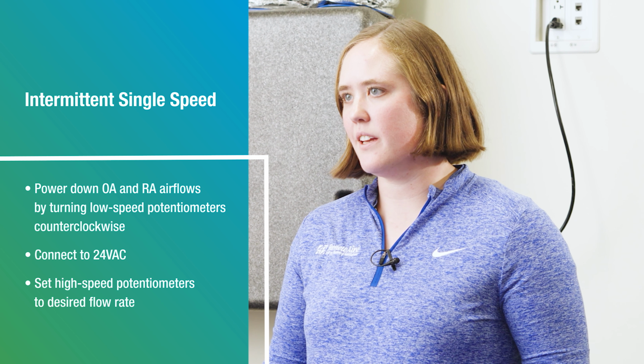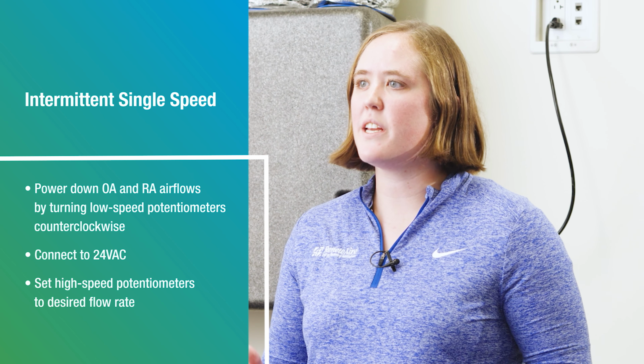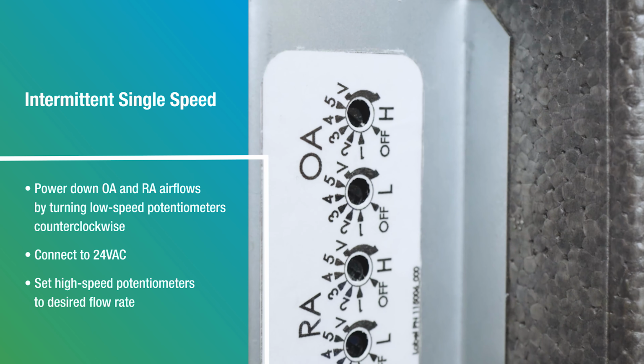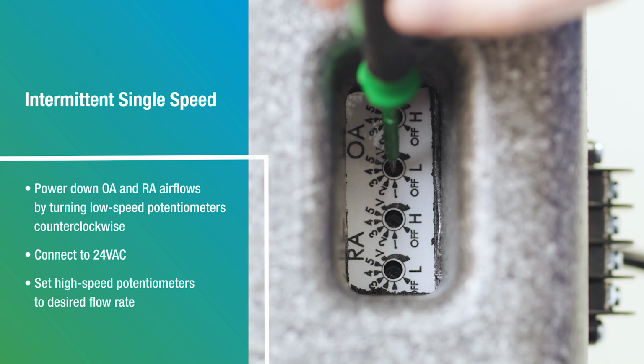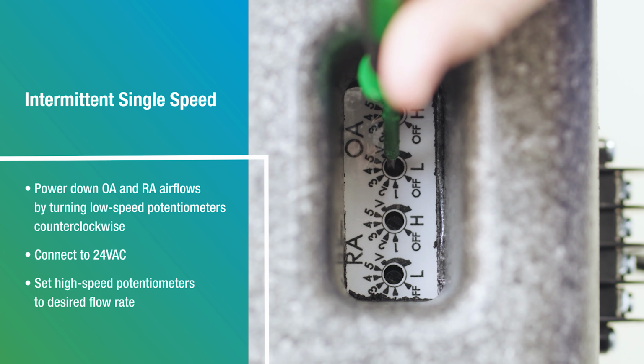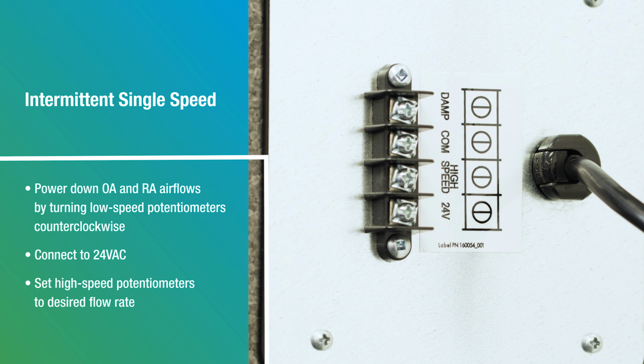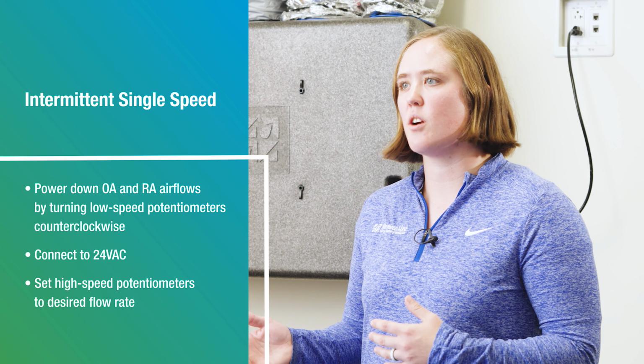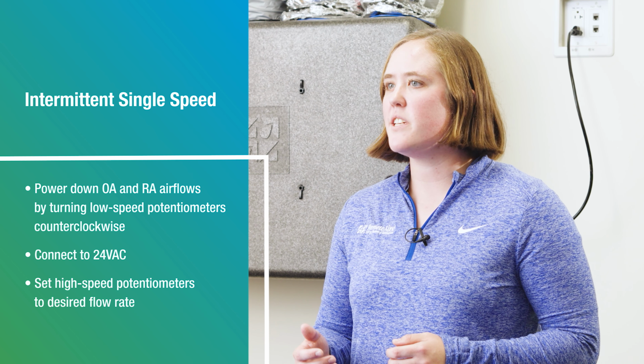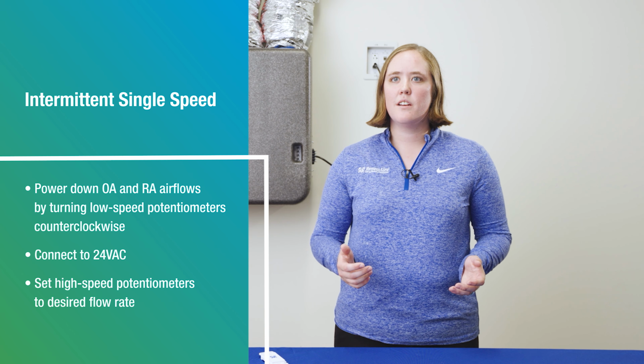To operate intermittently, an external controlling device must be connected. To do this, turn the low speed potentiometers counterclockwise to off for both the OA and RA airflows. Connect the controlling device to the 24 volt AC and high speed terminals on the unit. Set the high speed potentiometers to the desired flow rate. When the unit is plugged in, there will be no airflow until the control accessory signals the unit to operate in high speed mode. The PTL control is an ideal accessory for this unit, as it can be set to activate the ERV for a selectable repeating percent of every hour.